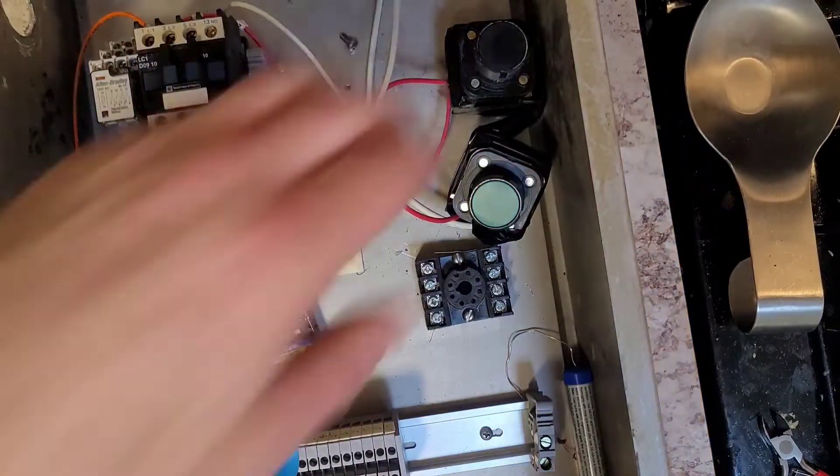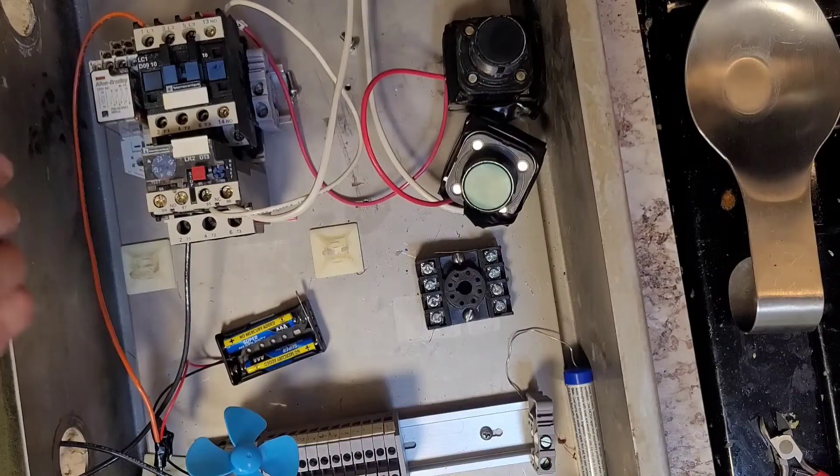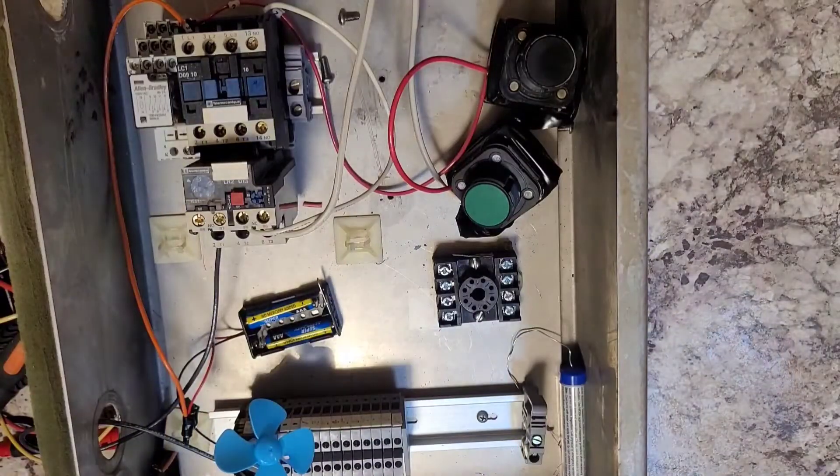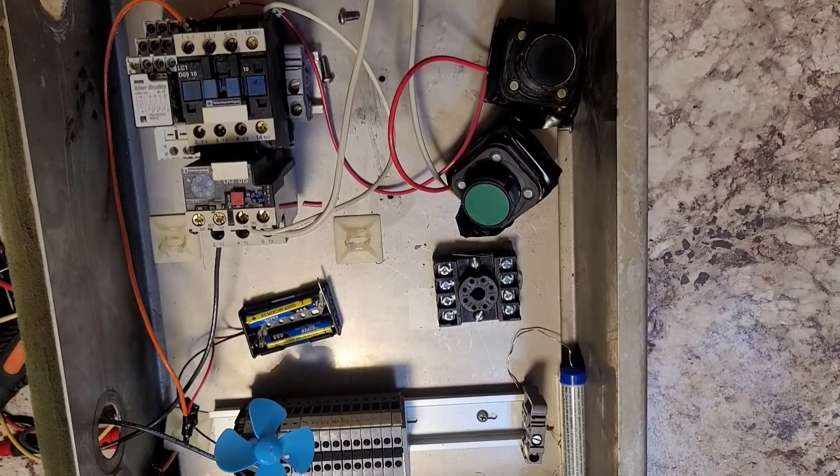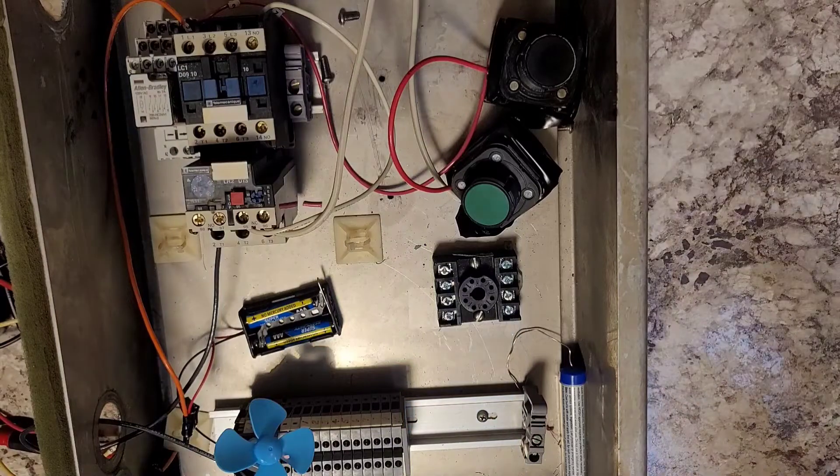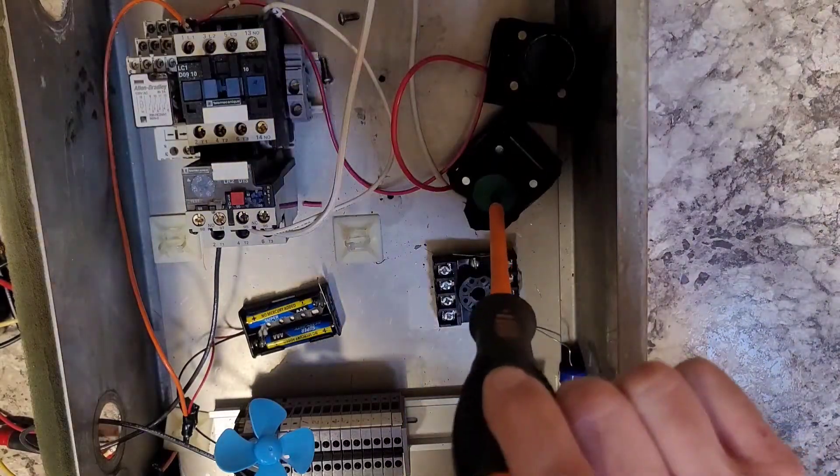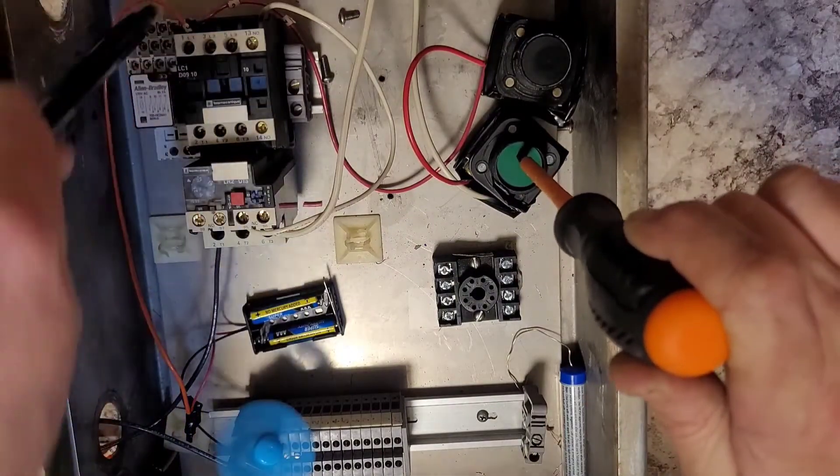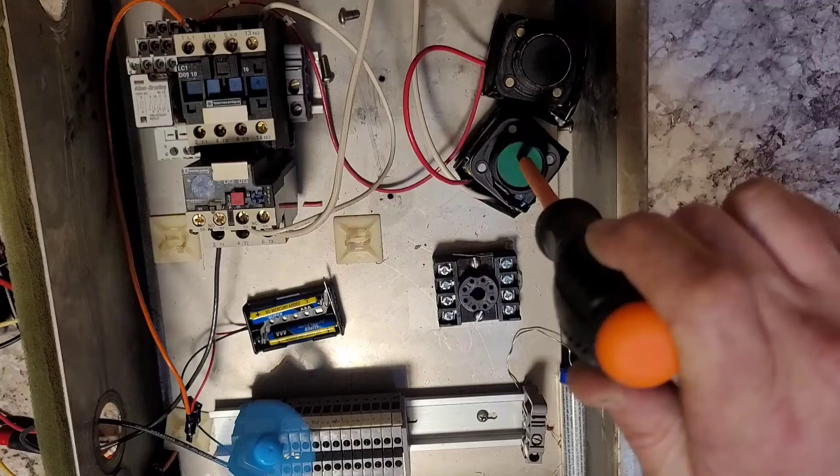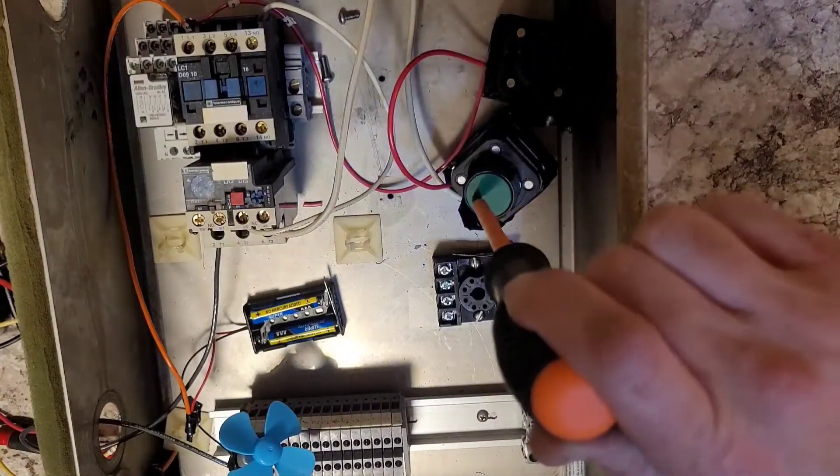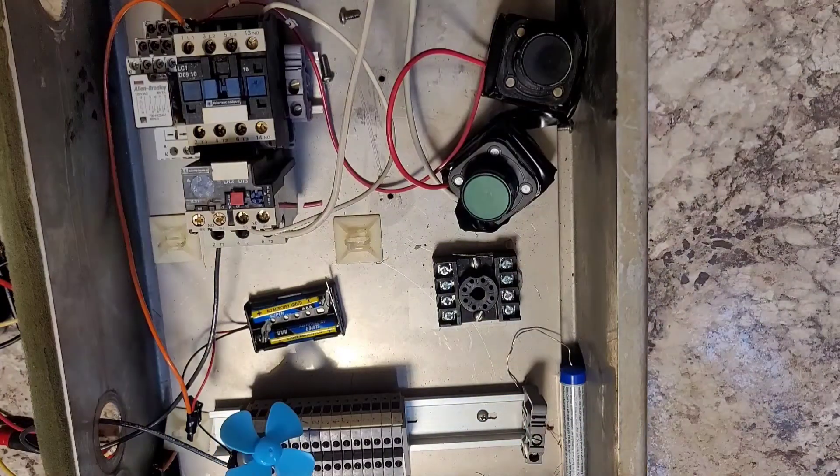Down here I added a nice little fan so I can demonstrate properly. I'm gonna plug this bad boy in. Here it is, the tension is mounting. I'm plugging it in, and surprise surprise, nothing happened. Let's see what happens when we hit our start button. Whoo! Our contactor pulls in and our circuit energizes. And then when I let go of the start button, it turns off.